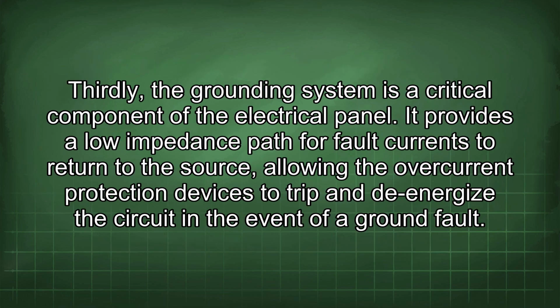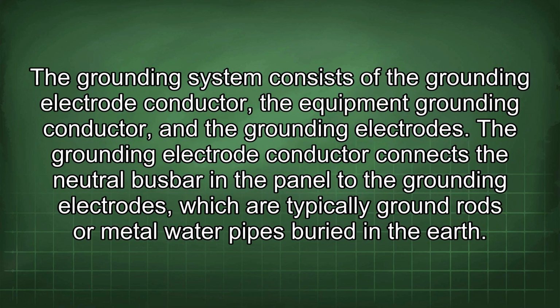Thirdly, the grounding system is a critical component of the electrical panel. It provides a low impedance path for fault currents to return to the source, allowing the overcurrent protection devices to trip and de-energize the circuit in the event of a ground fault. The grounding system consists of the grounding electrode conductor, the equipment grounding conductor, and the grounding electrodes. The grounding electrode conductor connects the neutral busbar in the panel to the grounding electrodes, which are typically ground rods or metal water pipes buried in the earth.